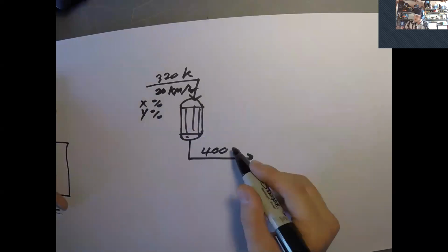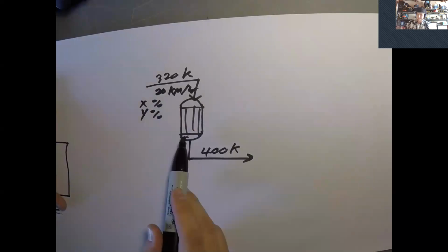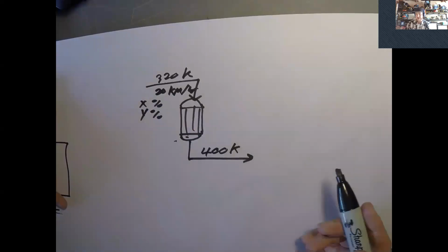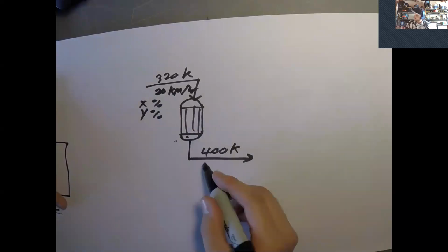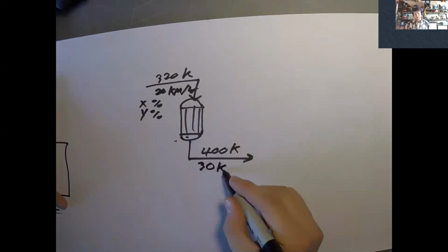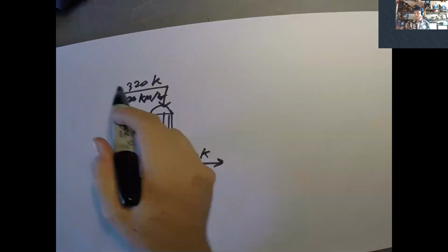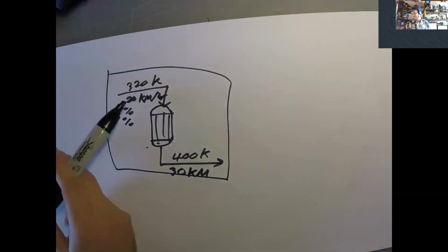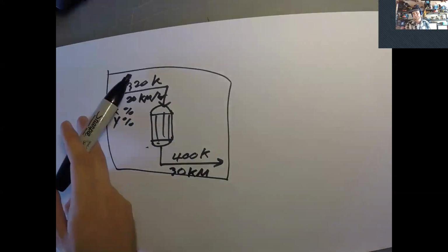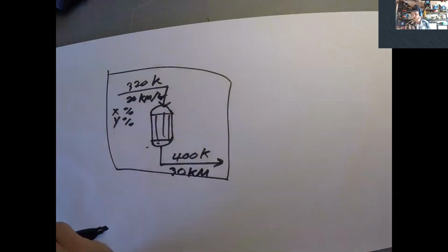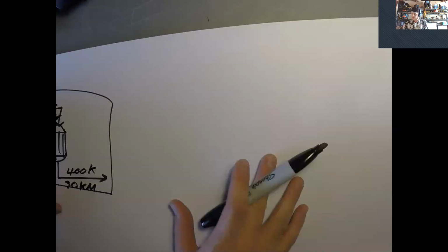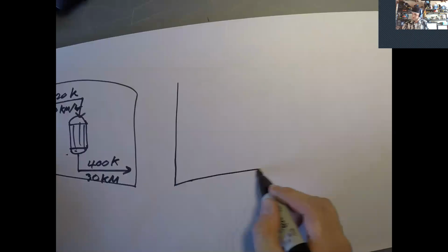Let's say this is an exothermic reaction, and there's no temperature control in the reactor, right? And you're generating stuff. But you call all these out. So this kind of thing that we're used to seeing, you don't usually call out flow rates and temperatures of a product stream on a P&ID, or even operational parameters. What you do call out is going into our example again.